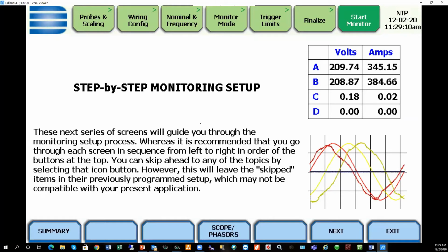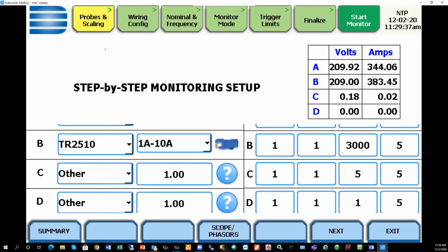In 2014, it's usually referenced to the fundamental. Total demand distortion, TDD, is referenced to your maximum demand current. Because there is no ITHD in the standard, as Ross mentioned earlier, it is referenced to demand current. So if your compliance is going to involve TDD, then there are some things you need to be aware of in the setup. But the approach, as far as probes and scaling, is pretty straightforward.